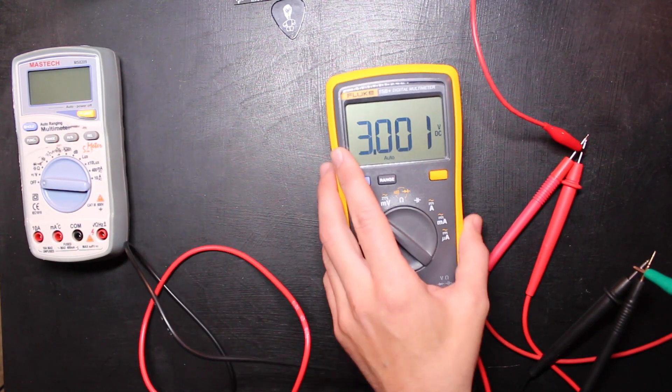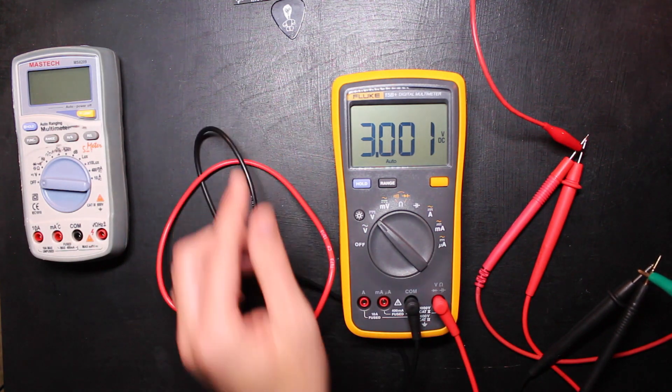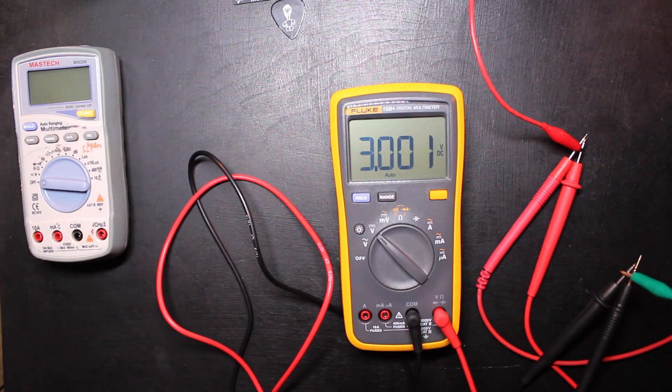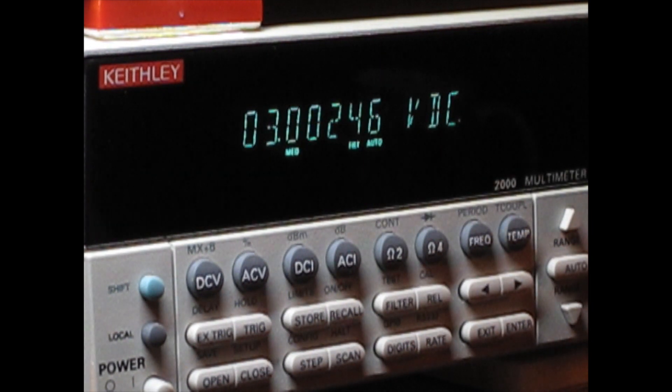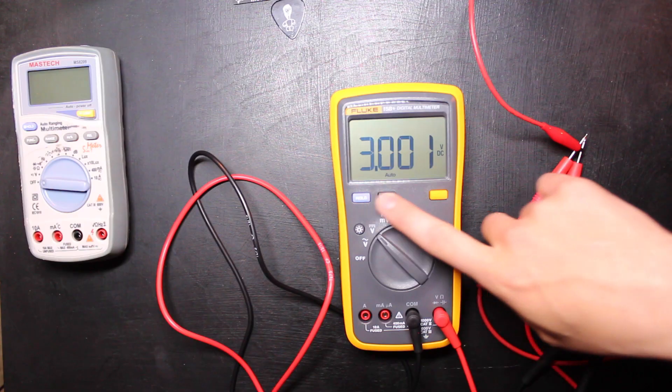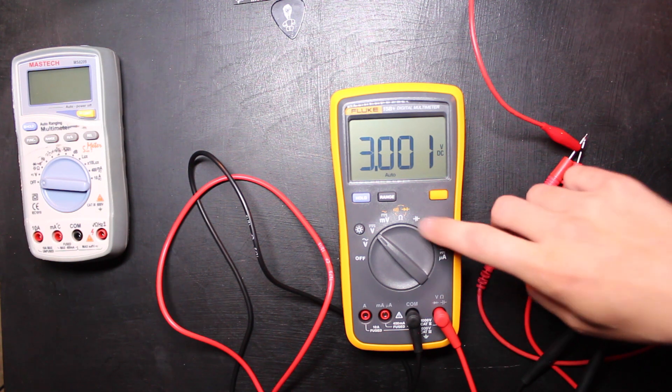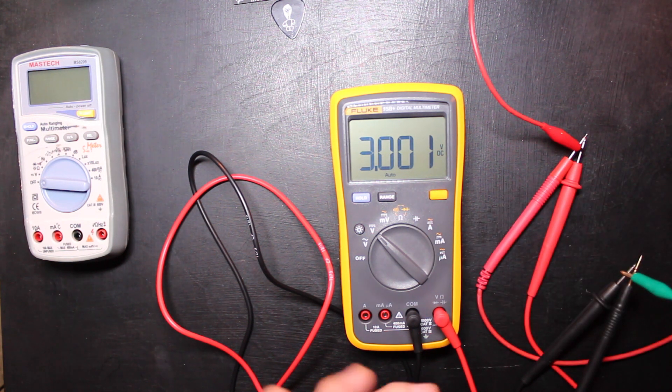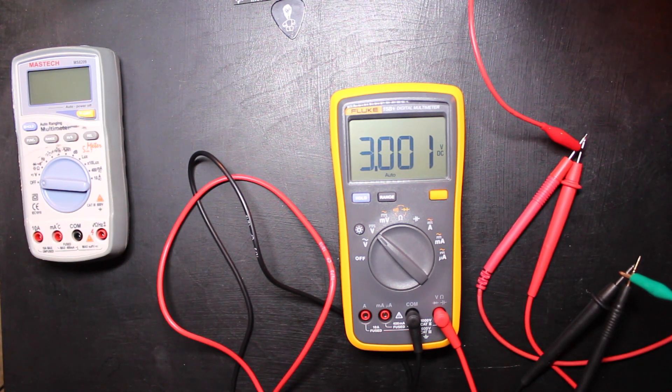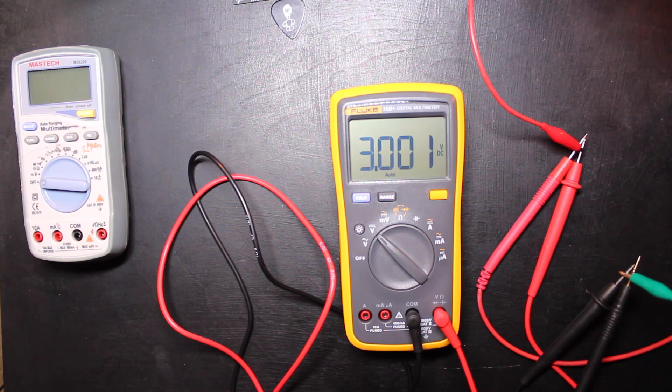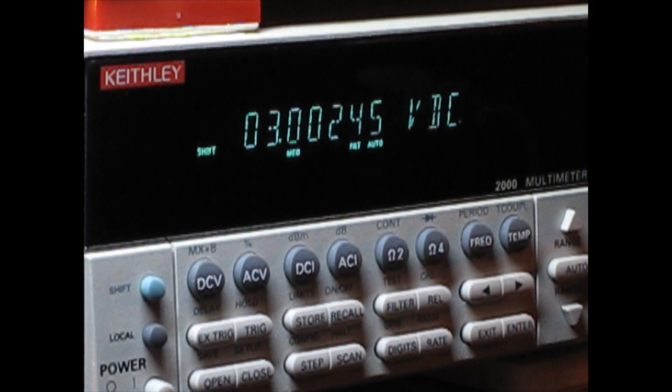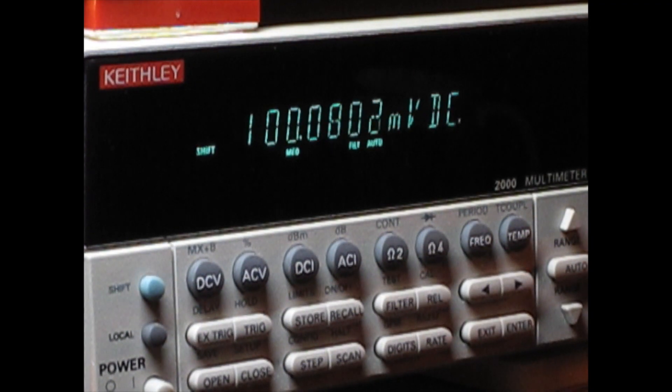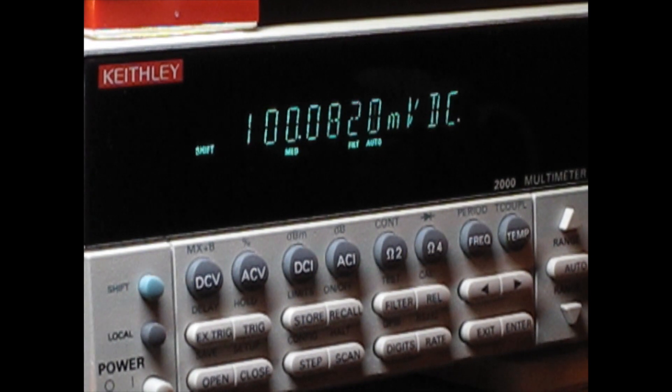Okay, so we're gonna measure voltage here first and you can see right now I'm putting three volts into it. The calibrated meter up here is 3.002, we're getting 3.001 over here on the Fluke and that's perfectly fine. So let's go ahead and drop this voltage down now. Okay, so there's a hundred millivolts and you can see here we've got 100.08.